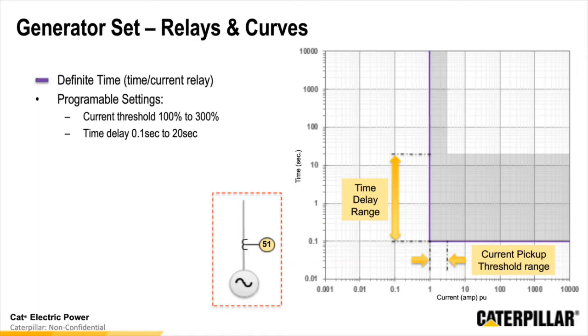to stop producing current. So as we've shown here in the graph, we have a purple line representing that 100% for 1/10 of a second. And then the gray section is really showing all the potential variation that you could make those settings to. Now, setting it to 100% for 1/10 of a second is probably not likely in most applications because as soon as you hit that full rated current of the unit, within 1/10 of a second, you're going to get a signal that's going to tell you that you need to shut the generator off. And that's not necessarily what you would want.